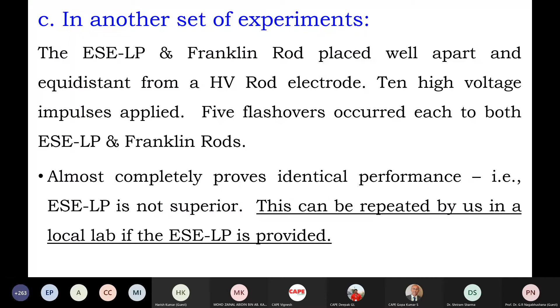The cloud bottom in real life is 2,000 to 3,000 meters above ground or the grounded object. Of course, the grounded object is also the ESE or the Franklin rod. Therefore, 2 meters spacing between the ESE LP and the copper plate is absolutely inadequate, unthinkably inadequate. Note that the height of the ESE LP itself is 2 meters. And then how can 2 meters between the tip and the copper plate represent the height to the cloud? And then the electric field will be terribly different.